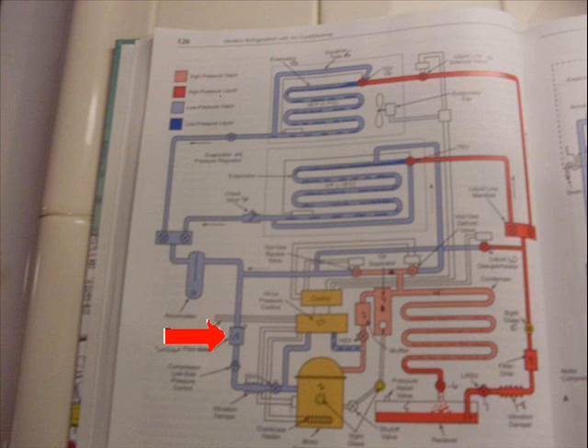Now, we go back down where our two evaporators tee back together. And on our way back, we'll probably run into a suction filter. The suction filter's job is to remove acids and solid particulate matter. The acids are hydrochloric, hydrofluoric, and nitric. And like I've said before, I am sure there's a whole bunch more acids I don't even know about with the new refrigerants.